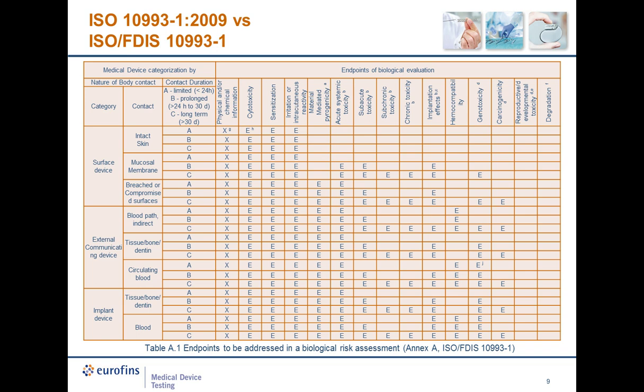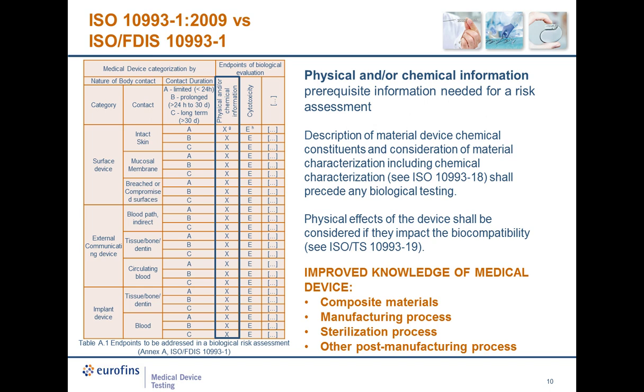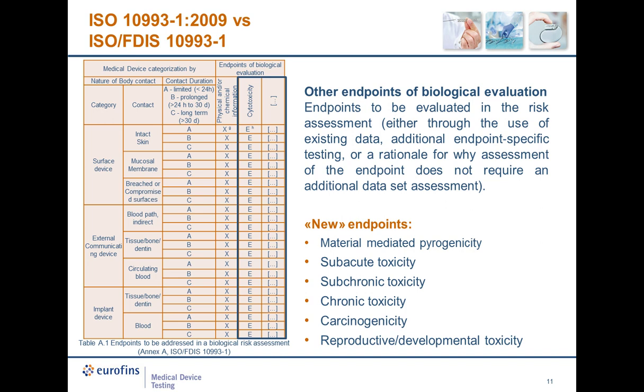Now, with the new part one, this approach of having chemical data as a starting point is more clear, even if the table seems more complicated. Physical and/or chemical information are a prerequisite information needed for a risk assessment. Description of constituent and consideration of material characterization shall precede any biological testing. Chemical characterization is described in ISO 10993-18, that is now under revision.